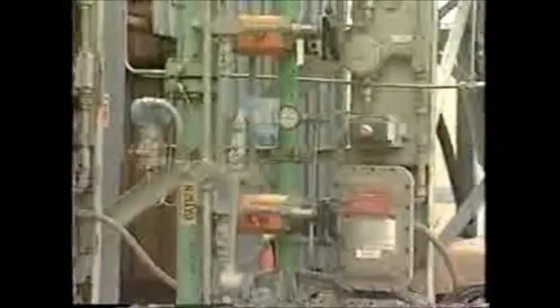Combustion chamber with pure oxygen. The oxygen-enriched air prevents the formation of products of incomplete combustion, which can form in less sophisticated systems. As an added safety measure, the TIS-5 is equipped with an independent auxiliary burner located within the secondary combustion chamber to ensure that complete thermal treatment continues in the unlikely event of a power failure.